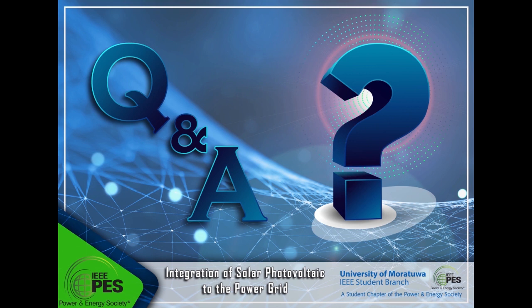In the high level diagram of control, I only showed maximum power point tracking and the current control in the in-phase component. We can also have a quadrature component control. With that, we can try to control the AC side voltage of the inverter. Of course, that means you are injecting reactive current, and the converter current capability is strained. If we are not injecting a lot of active current, then we have margin, especially during the night when there's no solar generation. You can use the full current capacity of the converter to support reactive power. With no in-phase component of current, the full current rating can be reactive current. That means you can serve as a voltage regulator.